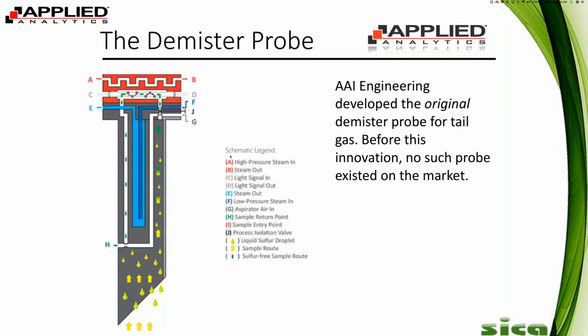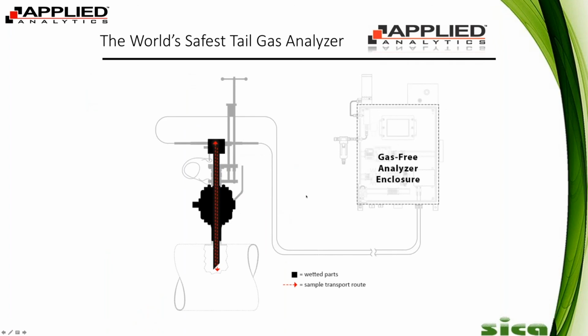And in the next slide, you'll see a representation of the separation of wetted parts and electronics, more specifically with the tail gas analyzer. So you can see the wetted parts are all in the probe. The sample just goes up and down the probe, and the measurement is made right in the head of the probe. Like I said, you don't want to come in human contact with these samples, and you don't want it to come in contact with your expensive electronics. So the probe is totally steam driven. There's no electronics in the probe. And yeah, so that's a major safety precaution of ours, the separation of wetted parts and electronics.